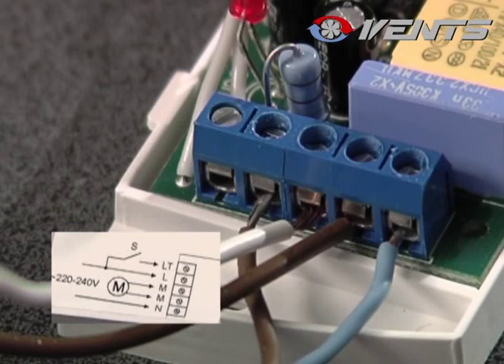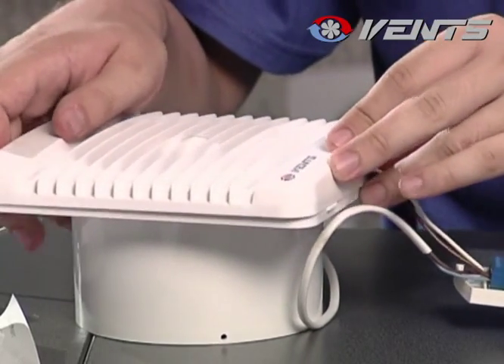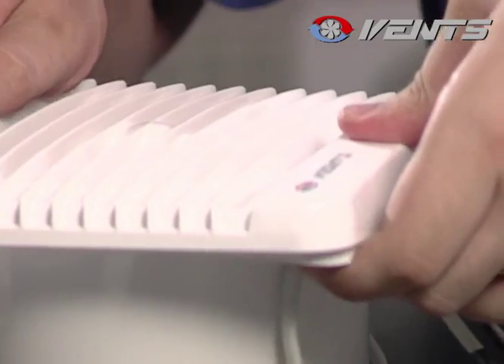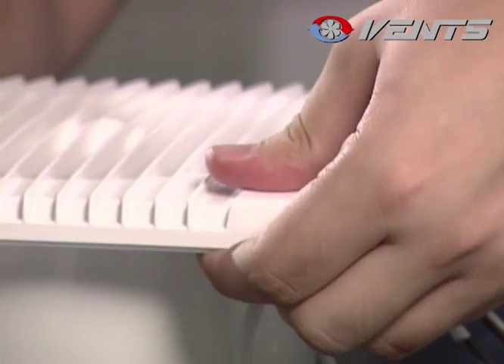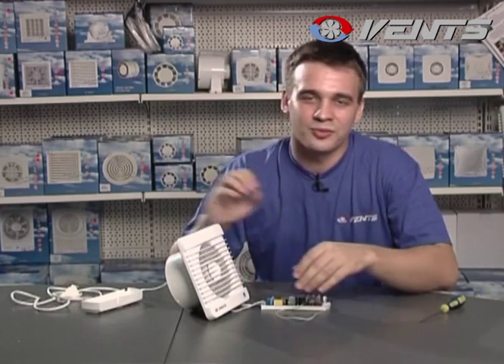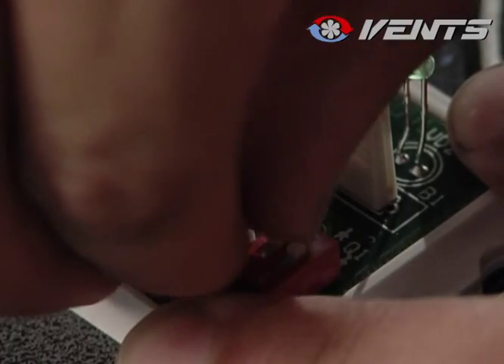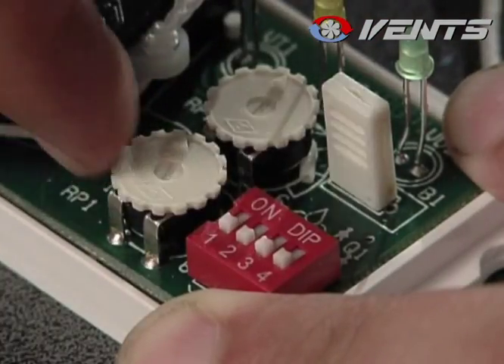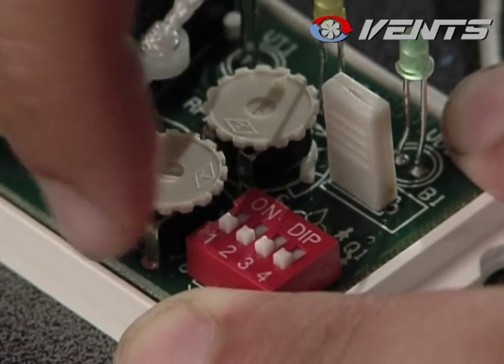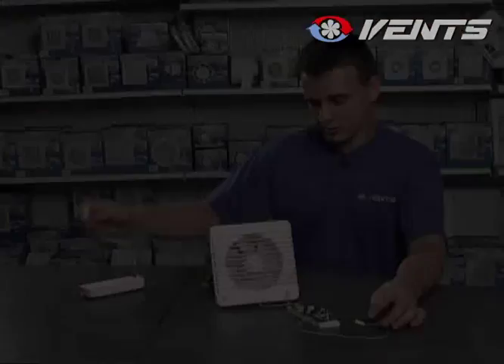LT terminal is for connection of the external switch. To check the correct connection of the fan to the control unit, turn all four jumpers to lower positions and set both regulating knobs to one position. In this mode, the fan will automatically switch on and off every five seconds.